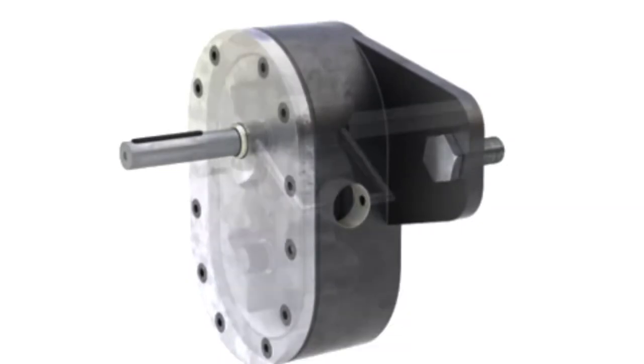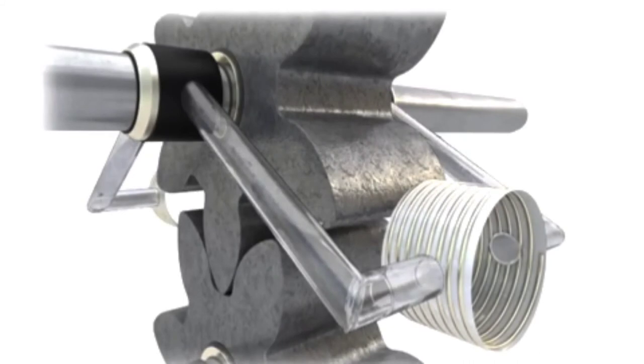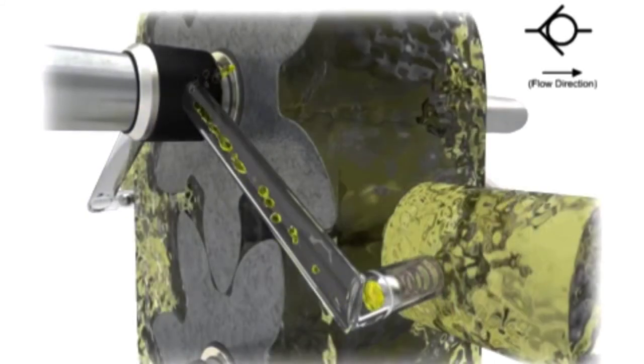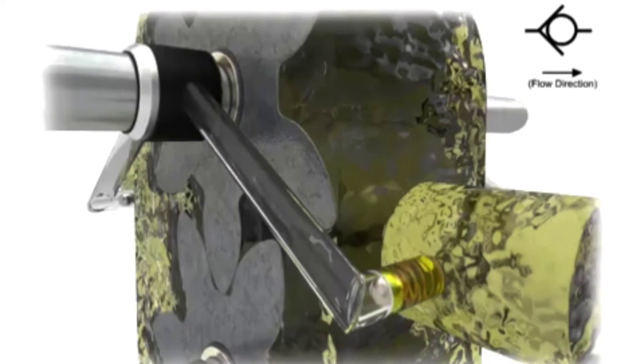Another method to prevent fluid buildup uses internal check valves. These valves allow accumulated leakage to flow in a specific direction to either main port, but will prevent backflow of high pressure into the bearing and seal pockets around the shaft.